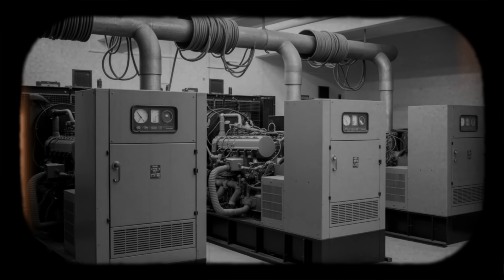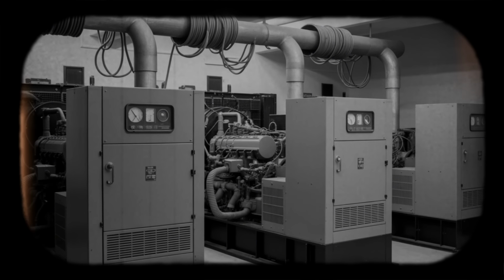From an obscure incident in a closed East German facility, Greifswald became a reference case, a benchmark for validating fire PRA models, a teaching example for cable duct vulnerability, and evidence that common cause fire could disable engineered heat removal systems across multiple emergency power trains. The reconstruction process revealed details: the 7.5-minute fault duration, the 120-meter extent of overheated cable, the 92-minute fire duration, the loss of 5 of 6 main coolant pumps, the multi-hour period of improvised cooling, the use of boron pumps outside design basis, the cross-unit power connection. Each detail refined international understanding of fire risk.